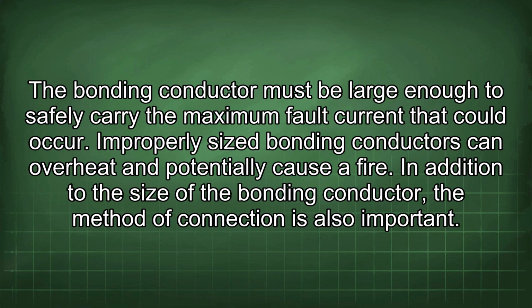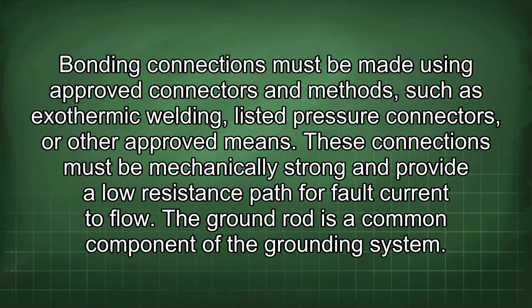In addition to the size of the bonding conductor, the method of connection is also important. Bonding connections must be made using approved connectors and methods such as exothermic welding, listed pressure connectors, or other approved means. These connections must be mechanically strong and provide a low-resistance path for fault current to flow.